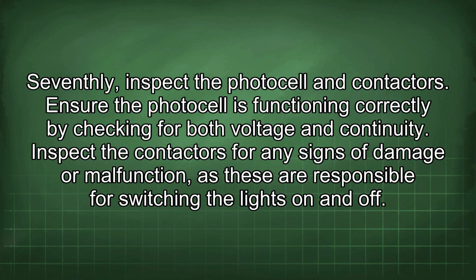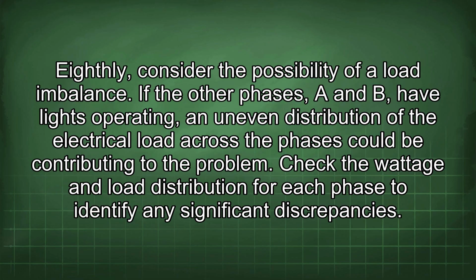Seventhly, inspect the photocell and contactors. Ensure the photocell is functioning correctly by checking for both voltage and continuity. Inspect the contactors for any signs of damage or malfunction, as these are responsible for switching the lights on and off. Eighthly, consider the possibility of a load imbalance. If the other phases, A and B, have lights operating, an uneven distribution of the electrical load across the phases could be contributing to the problem. Check the wattage and load distribution for each phase to identify any significant discrepancies.